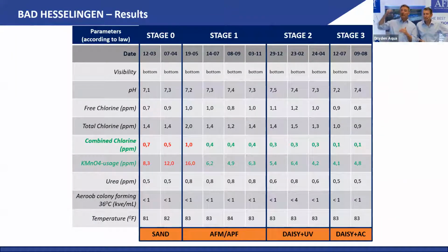Why? Because he lost a little bit of AFM, and then he was scared, and then the bed was not moving. And by the way, if you see here 19.5, this 5 is for May, and this was April. The results were good in week number 1, and then week 2 became less good, and after 5 weeks you were in this disaster. So they didn't change anything.